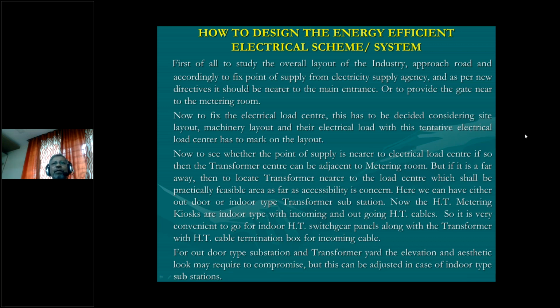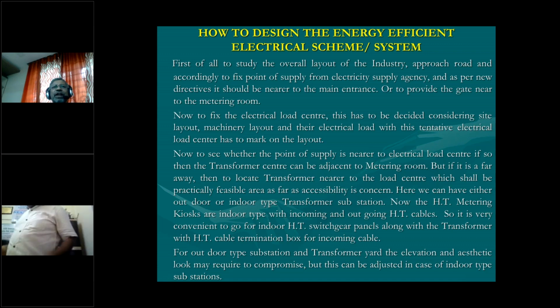Now to see whether the point of supply is nearer to the electrical load center. If so, then the transformer center can be adjacent to the metering room. But if it is far away, then locate the transformer near the load center, in a practically feasible area as far as accessibility is concerned. Here, we can have either an outdoor or indoor type transformer substation. Now, the HT metering kiosks are indoor type with incoming and outgoing HT cables. So, it is very convenient to go for indoor HT switchgear panels along with the transformer, with an HT cable termination box for incoming cables.